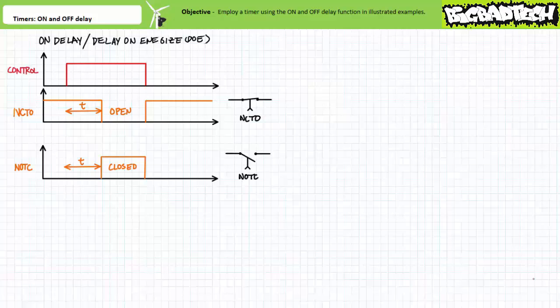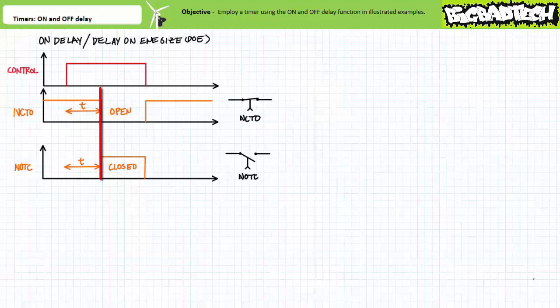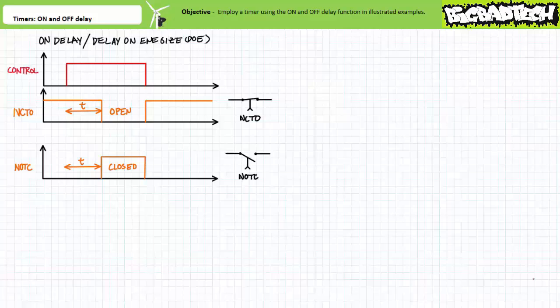Recall that a timing diagram of a timer executing the on delay, or delay on energized function, would look like this. When the controlling input is energized, the associated contacts do not instantaneously switch to their opposite state. Only after the predetermined delay period T has elapsed do the contacts change states. When the controlling input is de-energized, the contacts quasi-instantaneously revert to their normal deactivated state. The on delay timer could be used to turn another motor on a measurable time period after another has started.